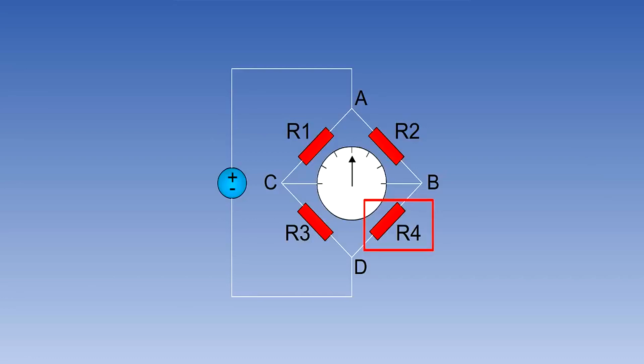If one of the resistors is exposed to the outside air as temperature changes, so will the resistance. This will cause an imbalance in the circuit and the current will flow, which will be proportional to the temperature change. The change in resistance is consequently a measurement of temperature change and can be calibrated.